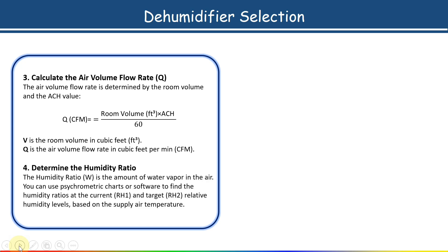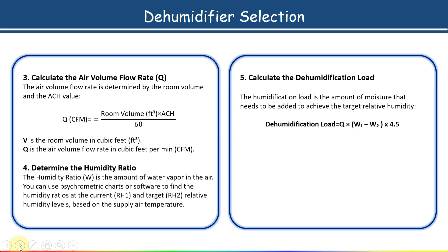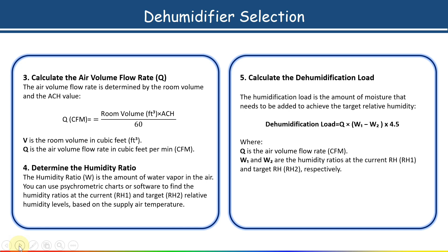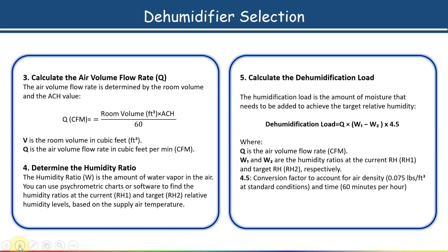Once you have the air volume flow rate, the next step is to determine the humidity ratio. Based on your current and target relative humidity levels, calculate the humidity ratio value from the psychrometric chart or from software. Then, to calculate the dehumidification load, the formula is: Dehumidification Load = Q × (W1 − W2) × 4.5, where Q is the air volume flow rate in CFM, W1 and W2 are the humidity ratios at the current and target relative humidity respectively, and 4.5 is the conversion factor to account for air density and time.